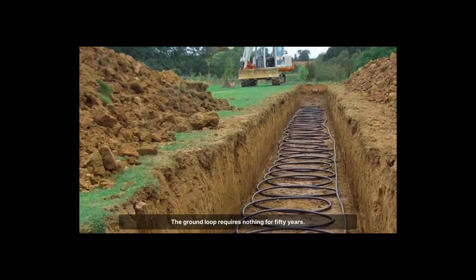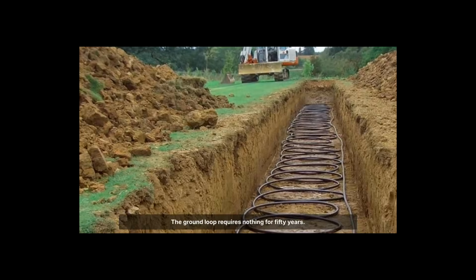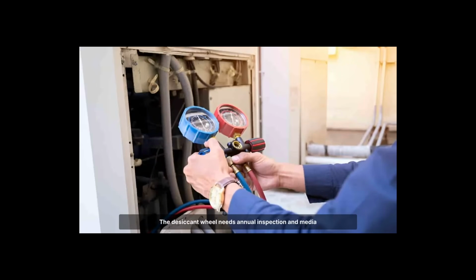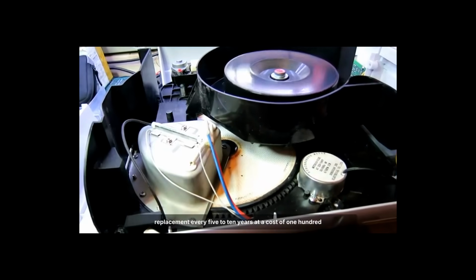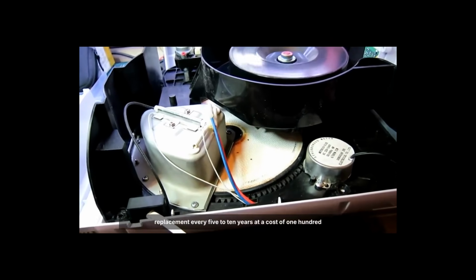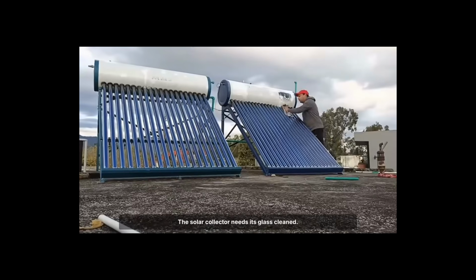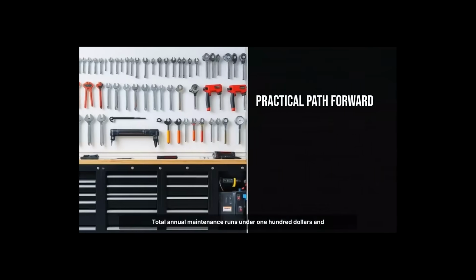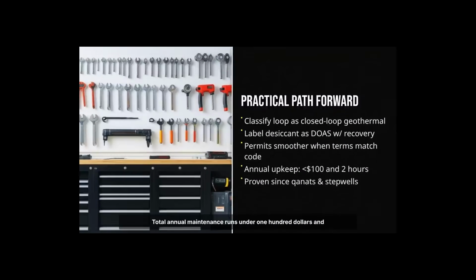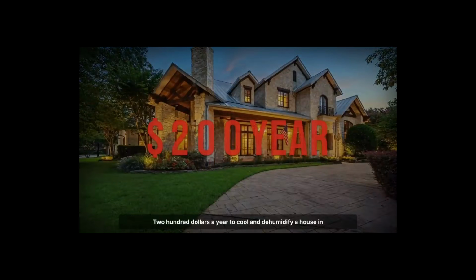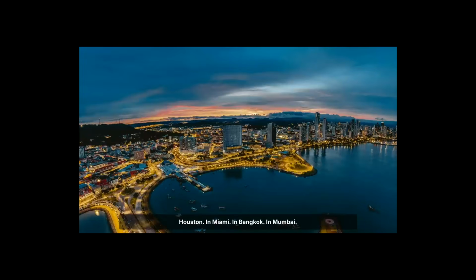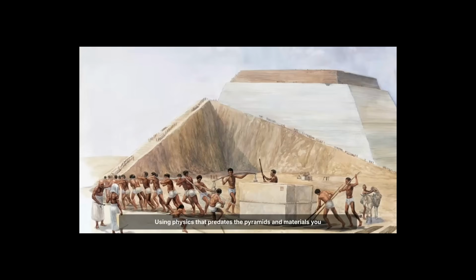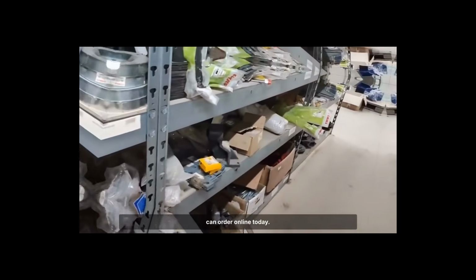Maintenance is minimal. The ground loop requires nothing for 50 years. The desiccant wheel needs annual inspection and media replacement every 5 to 10 years at a cost of $100 to $300. The solar collector needs its glass cleaned. Total annual maintenance runs under $100 and 2 hours of time. $200 a year to cool and dehumidify a house in Houston, in Miami, in Bangkok, in Mumbai, using physics that predates the pyramids and materials you can order online today.